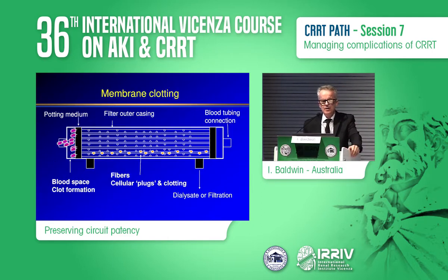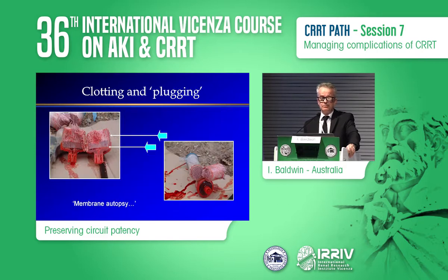So just to begin, we understand the membrane structure, but I'm just highlighting to you that when we do get failure, it's a clotting and a plugging or a clogging process. This is a little bit of work I did many years ago, entitled the membrane autopsy. You can see at the entry point into the membrane there is clot collecting there, obstructing the forward flow, and there may not be any significant clotting further down into the membrane, but there is certainly a clogging process.